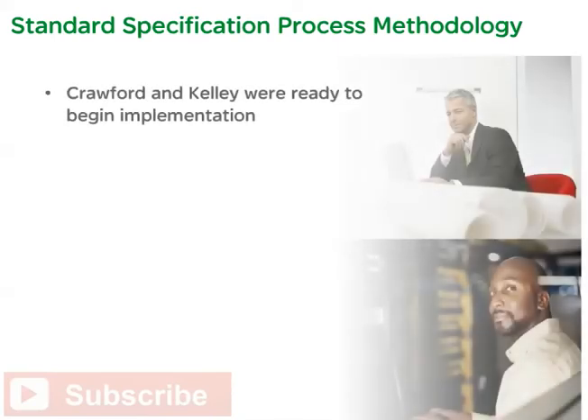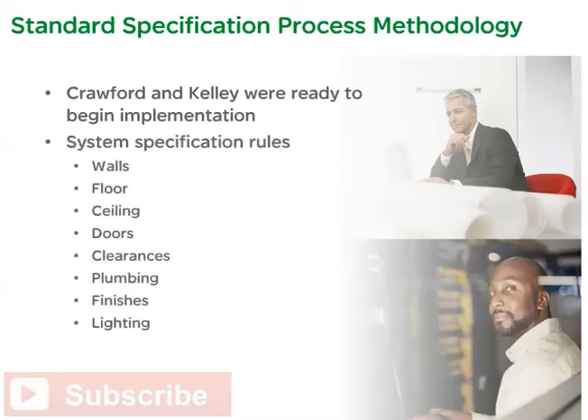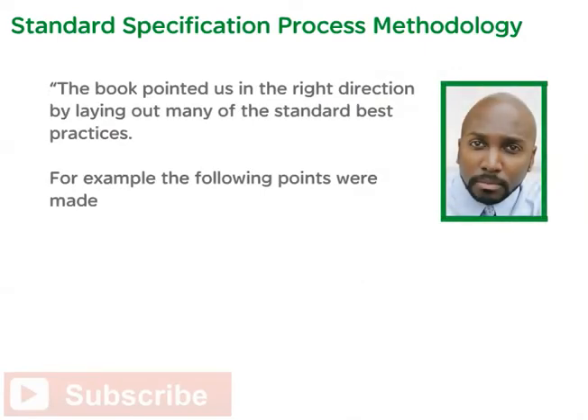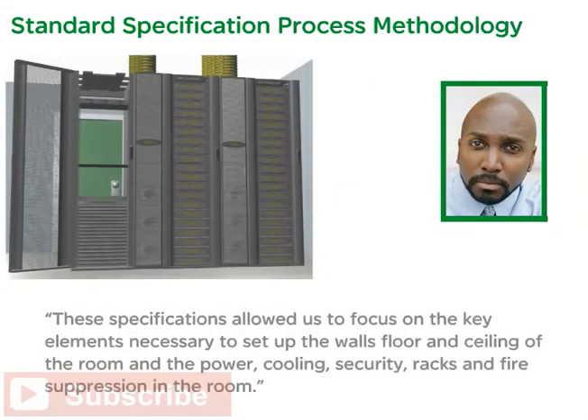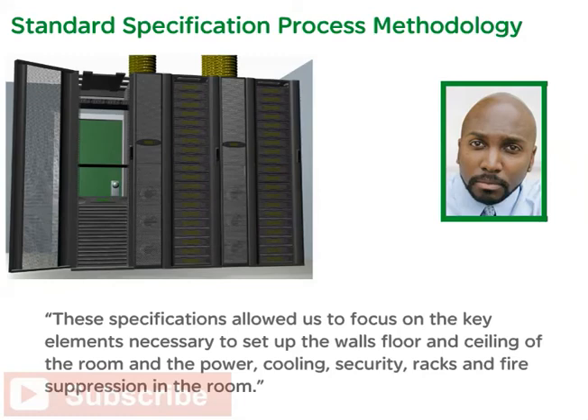With a well-written specification in hand, Crawford and Kelly were ready to begin implementation. Rules for walls, floor, ceiling, and doors, as well as clearances, plumbing, finishes, and lighting were all part of their system specification and project manual. The book laid out many standard best practices. For example: wall and flooring finishes shall reduce static electricity; floor shall not be carpeted; no exterior doors or exterior windows shall be present unless required by safety code; ceiling tiles shall be flush and level and shall not require the removal or displacement of mechanical or electrical infrastructure. These specifications helped the team focus on the key elements for setting up the walls, floor, ceiling, power, cooling, security, racks, and fire suppression.